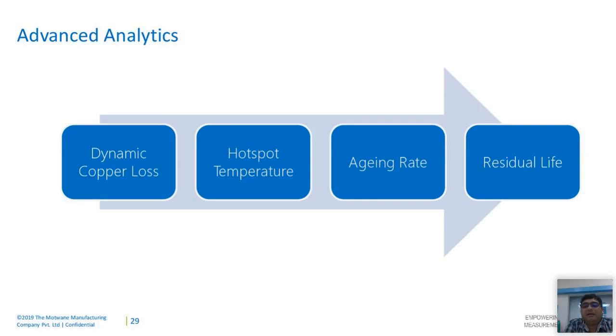So here we can incorporate two variances which have a bearing on the copper losses. One of them is the temperature impact on the change in the resistance value, and the second is the aging impact on the change in the resistance value over a period of time. Both these combinations can give you, in real time and dynamically, the losses happening in the windings of the transformer.